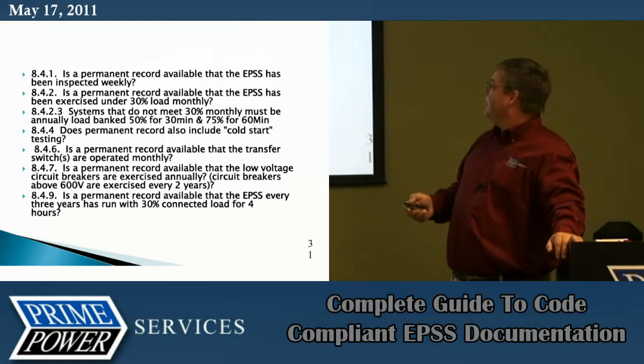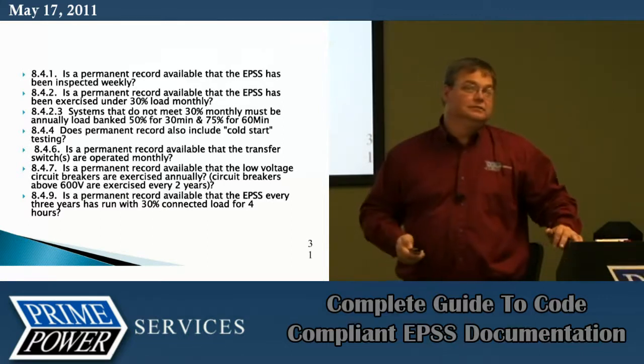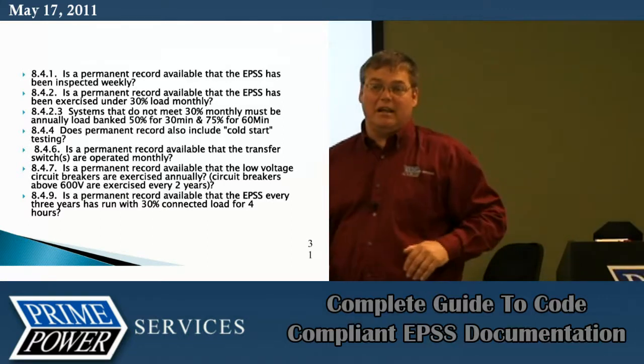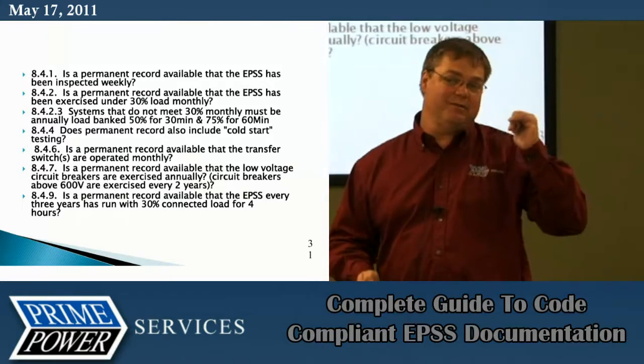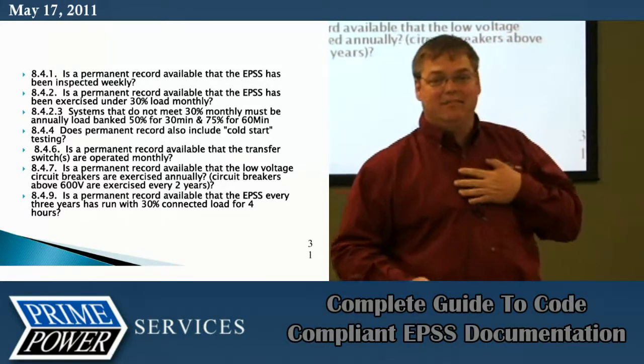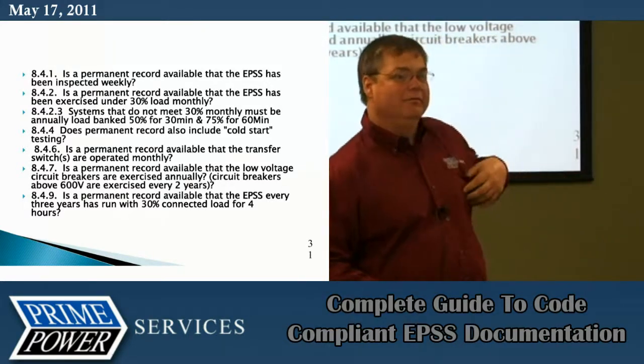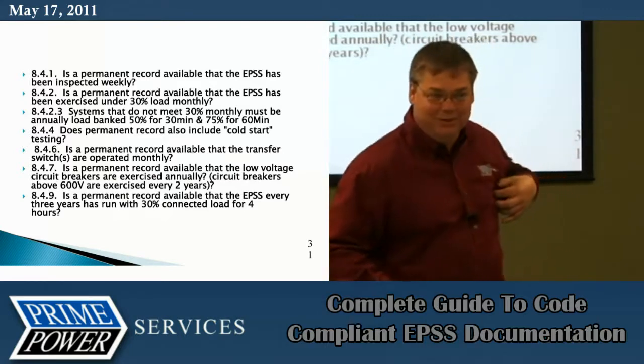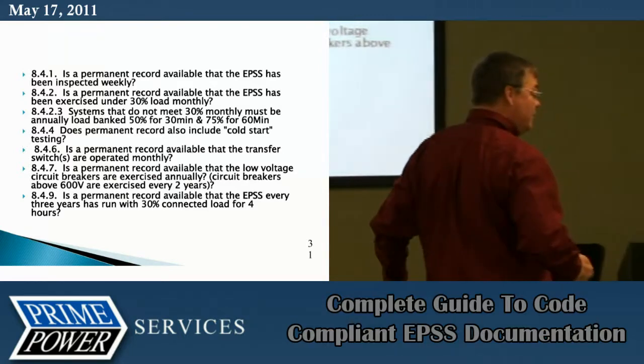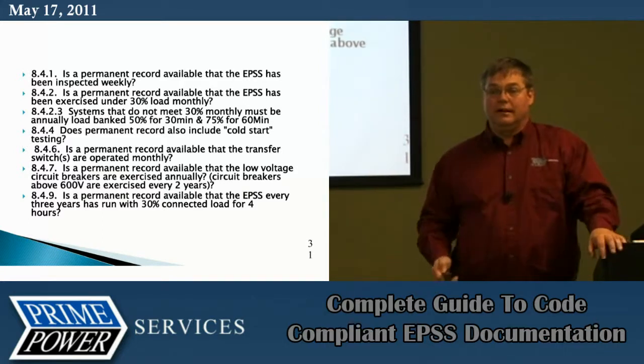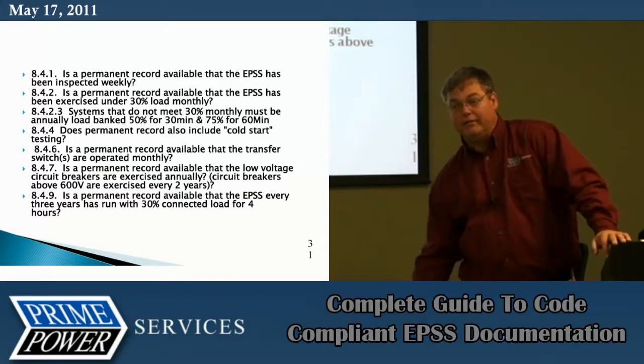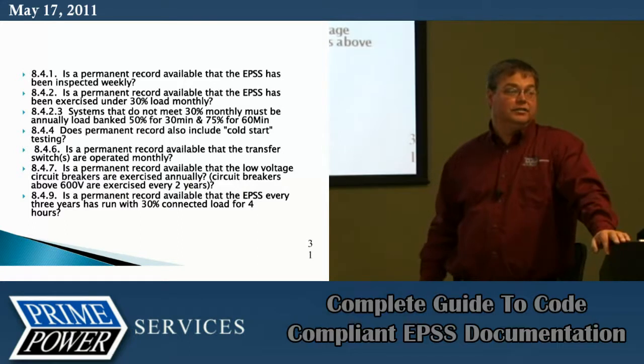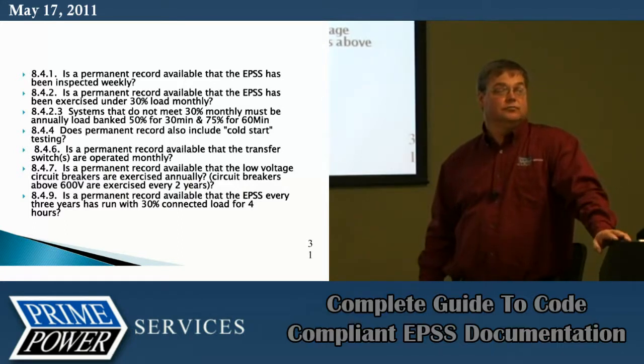Is a permanent record available that low voltage circuit breakers are exercised annually? Circuit breakers above 600 volts are exercised every 2 years. I'm not going to survey you because you might not want to give this answer, but I bet you half of you in the room don't do that one. I can tell you from a hospital perspective, I never done that one. And I won't do it until somebody makes me do it. But it is an NFPA code, and it is recommended. And the idea there is if you don't ever test them, when are they going to fail? It's not if they'll fail. They'll fail one day. That'd be 50 years, but that's just exercising.